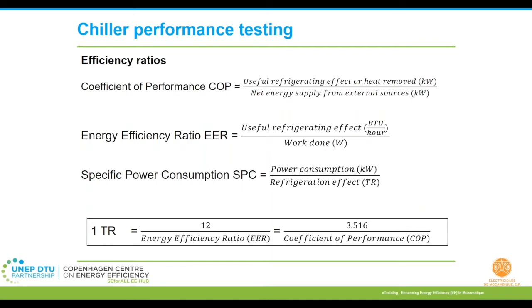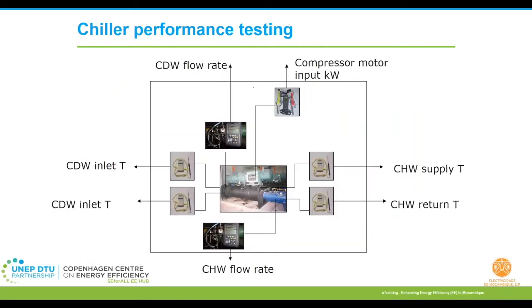You must have come across different energy efficiency ratios on different nameplates of HVAC systems. So to avoid any confusion, you can always look into this slide for conversions, because different suppliers represent the ratios in different formats. To compare on a similar level, you can use these conversion factors and definitions to compare the efficiencies of two different companies or two different air conditioning units. For a large building setup, generally they have these big chillers in place. When you're evaluating the chiller performance, you will need to either measure or take these parameters into account. If it is an auditing team that comes, they would be measuring these parameters. But also lately, most buildings are coming up with their own building management systems, where they capture all these parameters into a single control system and keep monitoring.